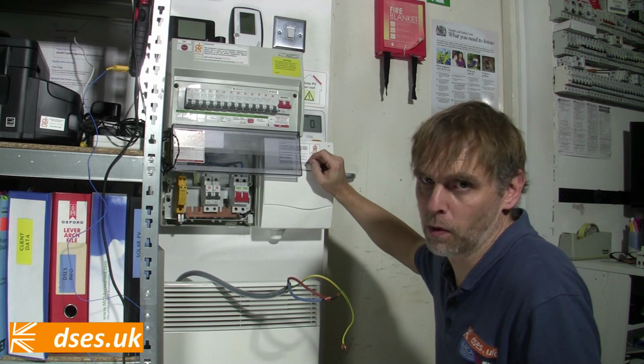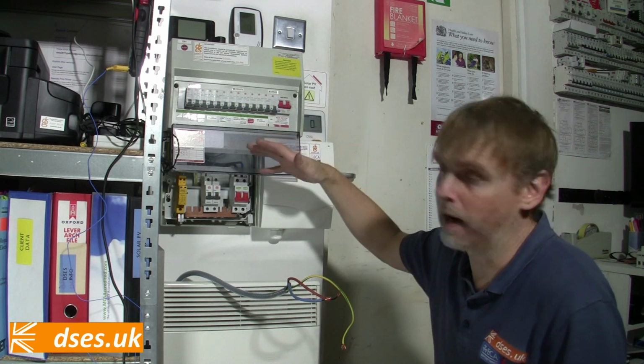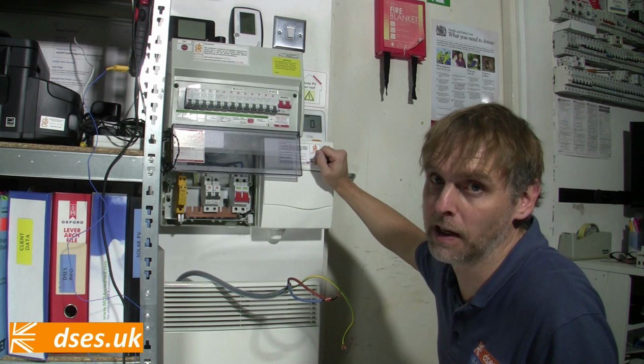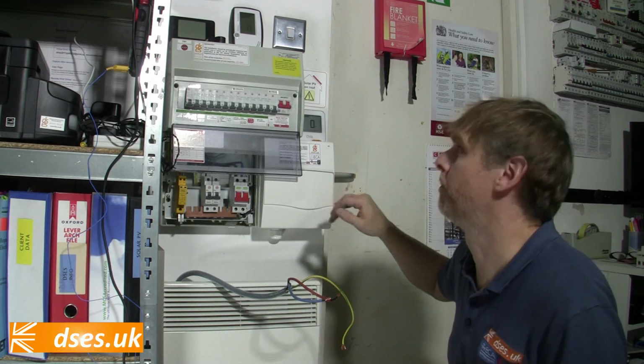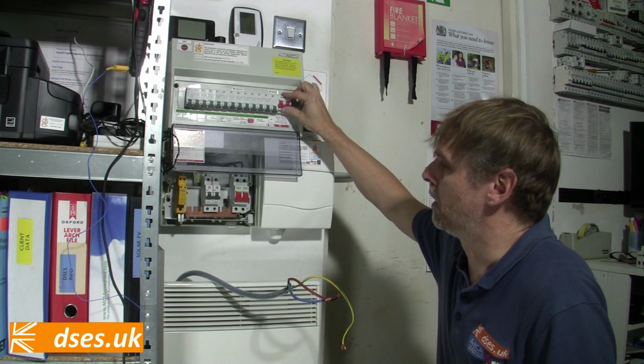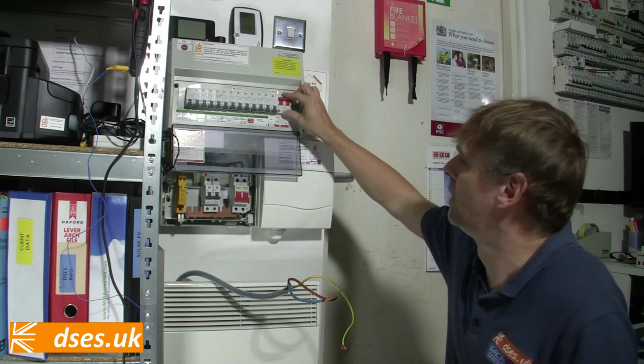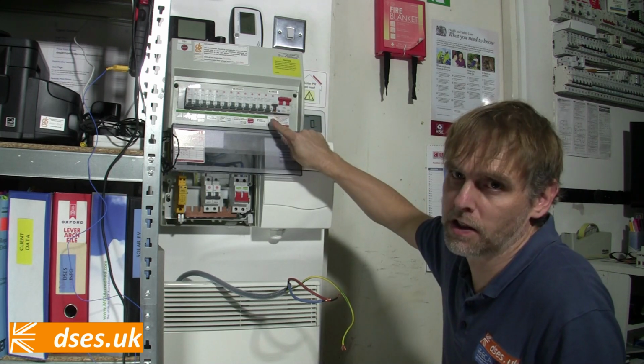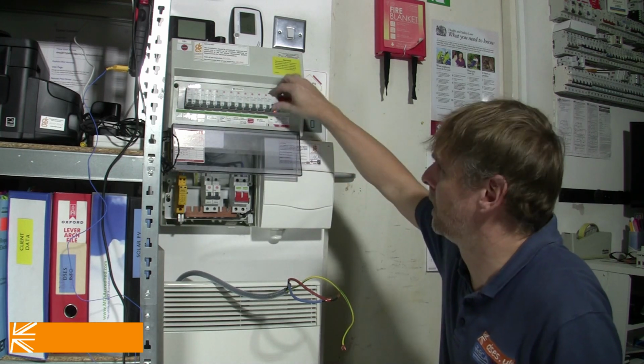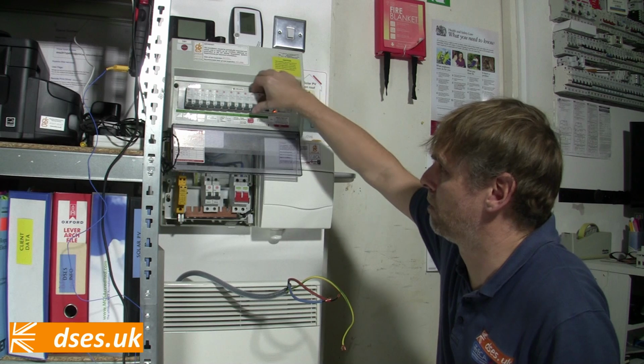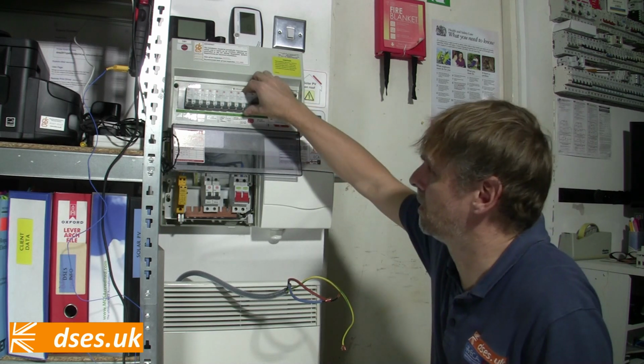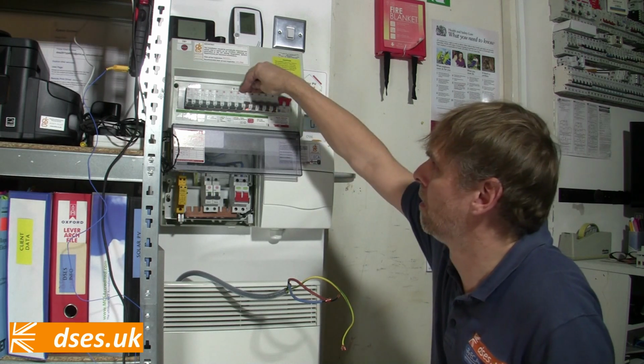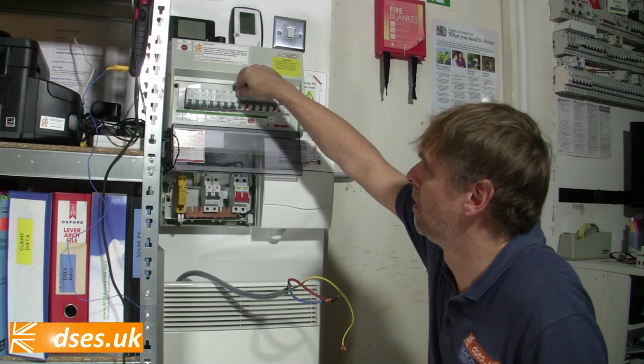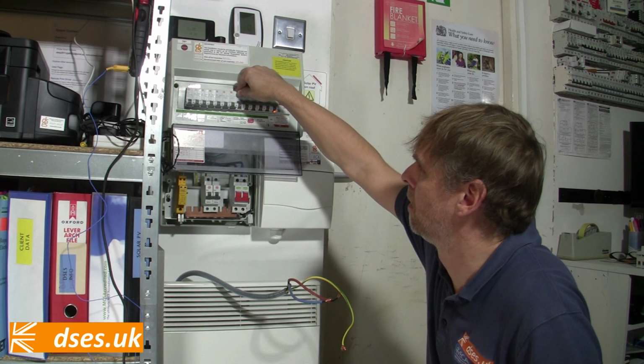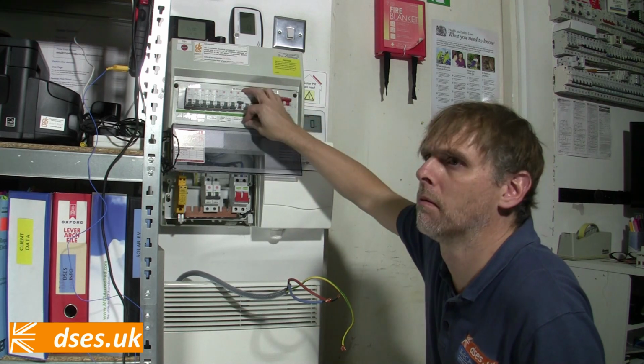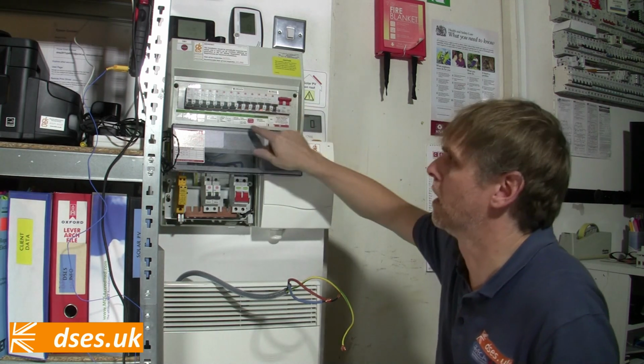And this will be the first time, of course, that my circuits have gone live with equipment connected on AFDD. So it'll be interesting to see if there's any nuisance trips from the off. There shouldn't be, because I've been through all this, as I'll talk more about later. We are going to see some flashing lights on here because when I was prattling about earlier, I haven't cleared the faults that I put on with my RCD tester or my AFDD tester. Yeah, I'm confusing myself because I'm looking at these wrong labels.